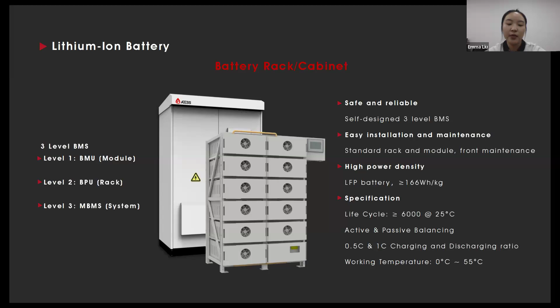The main difference between battery rack and cabinet is the protection level. Battery rack can only be installed in the operation room with AC or in our container, but the battery cabinet can be installed outdoors. It has AC and the fire suppression system integrated, and the protection level is IP54. The ATESS battery solution comes with a 3-level BMS, which enables easy installation and maintenance.